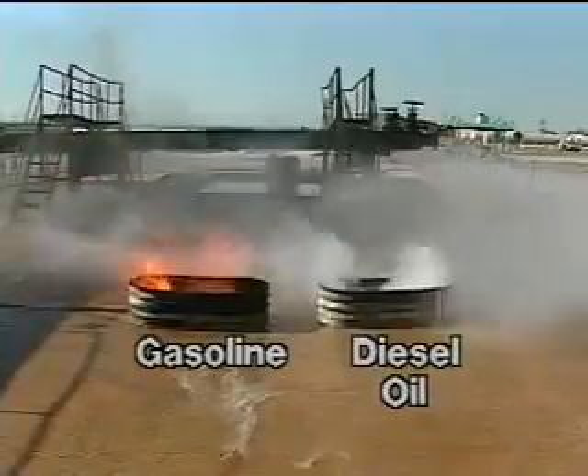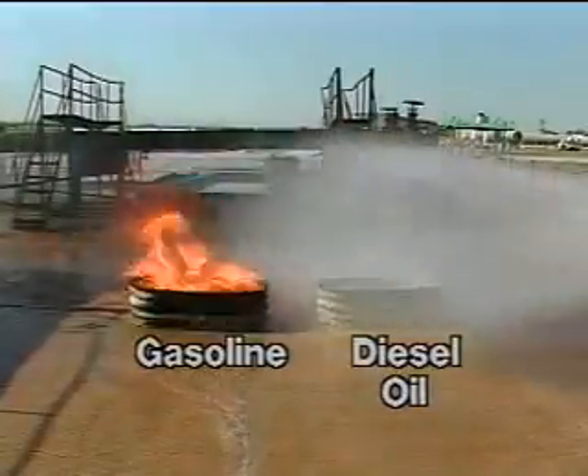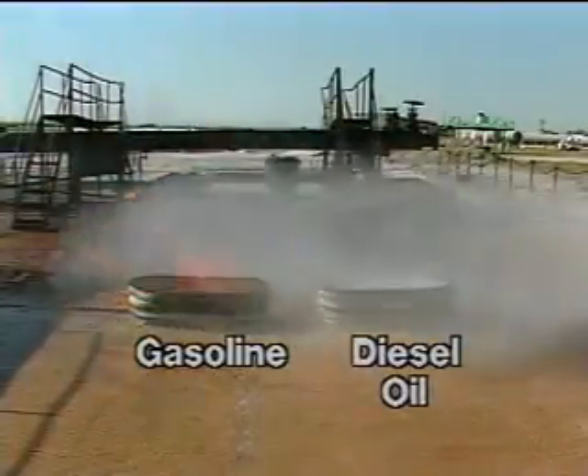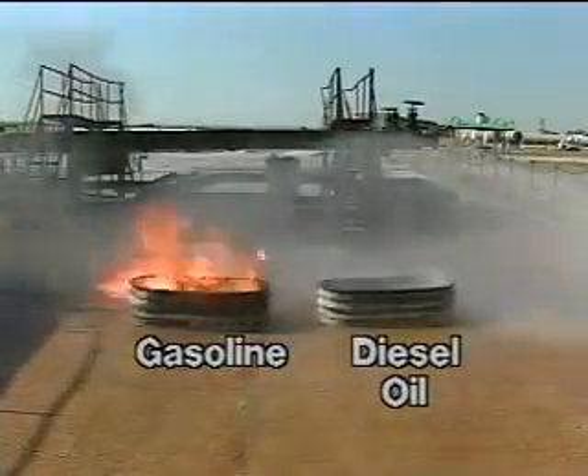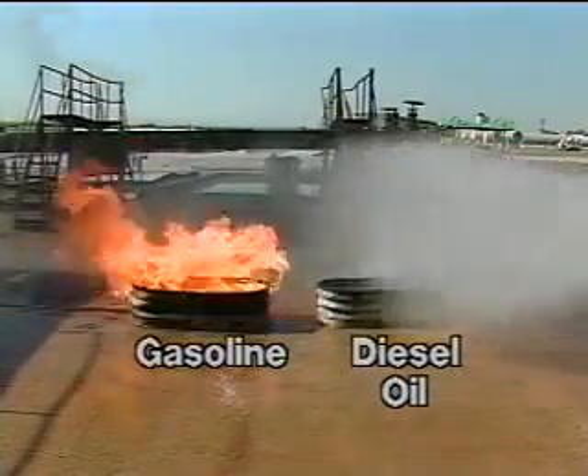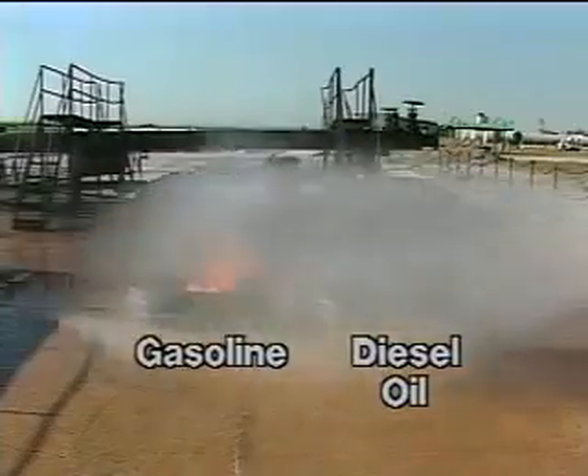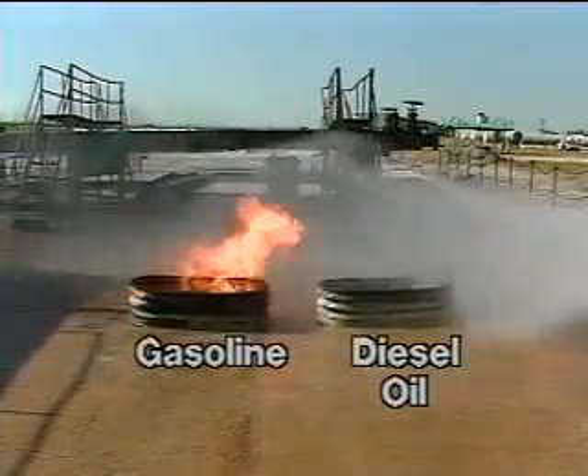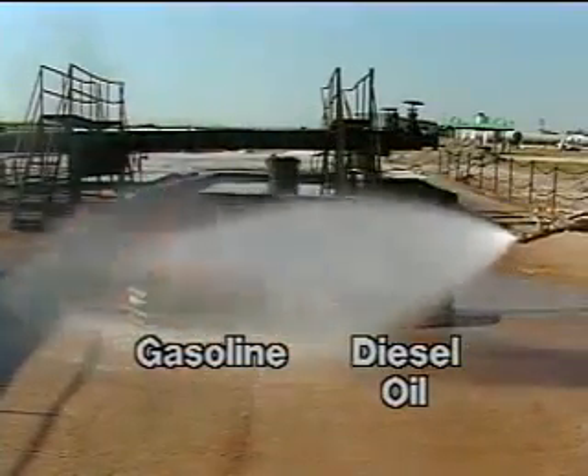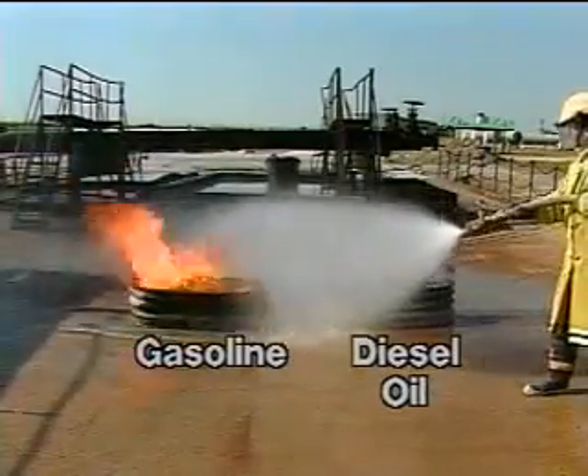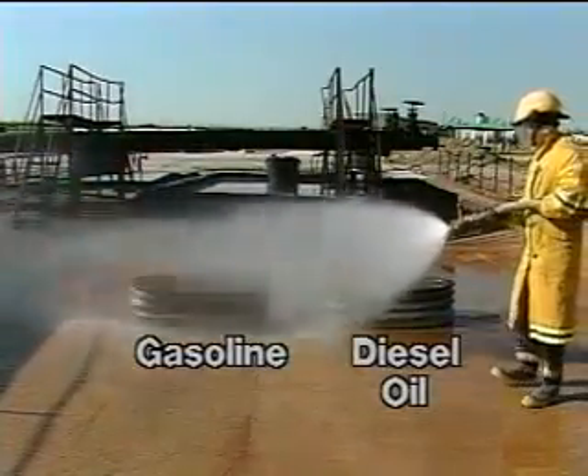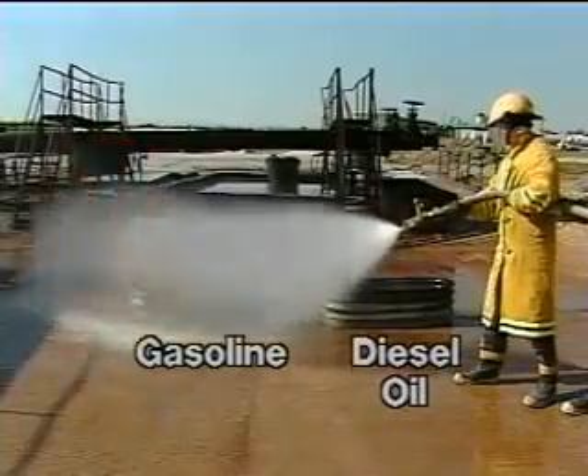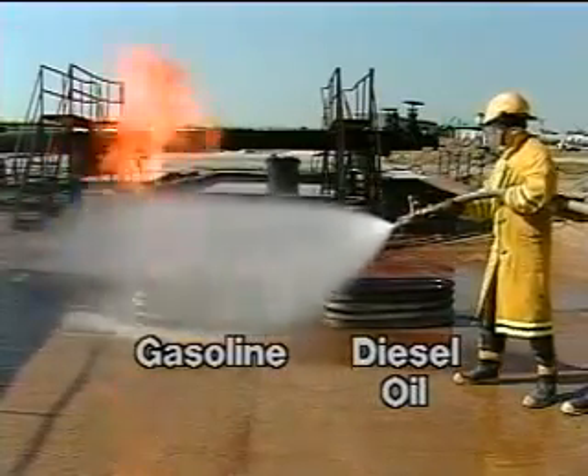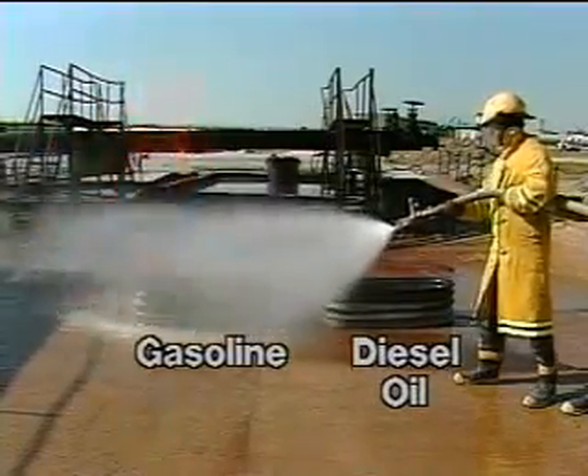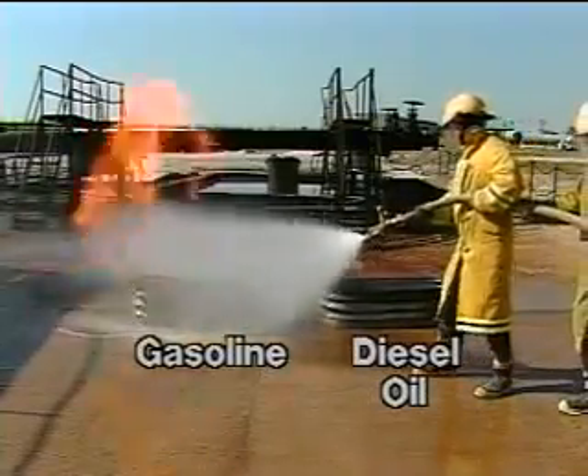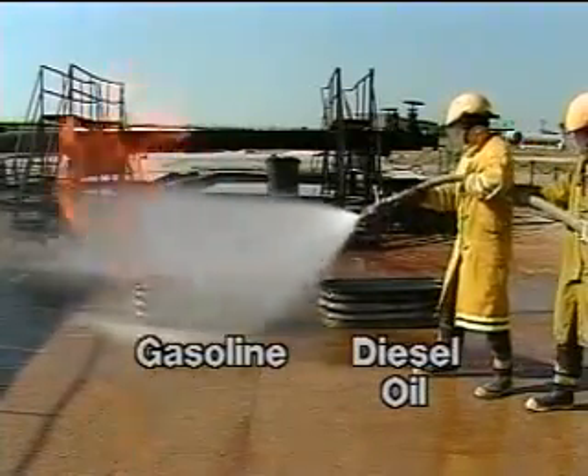That's because water can cool the diesel oil to below its flash point of 110 degrees Fahrenheit and stop the production of dangerous vapors. With burning gasoline, however, water cannot cool the gasoline sufficiently to stop the fire. Water freezes at 32 degrees Fahrenheit, a long way from gasoline's flash point. So even though gasoline and diesel oil fall under the same Class B category, different firefighting methods are used to combat fires involving these liquids.